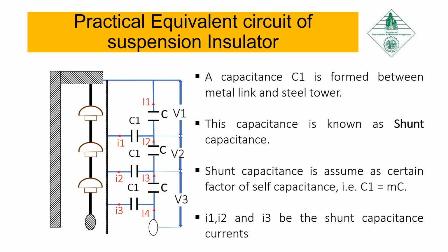In actual practice, the voltage across each unit is not the same because of capacitance formed between metal link and steel structure. Metal link and steel structure behave like conducting plates and in between air is the insulating medium.